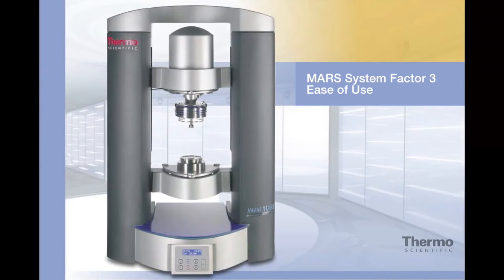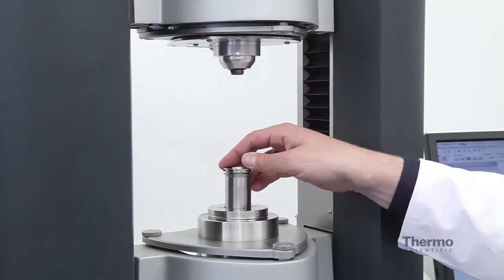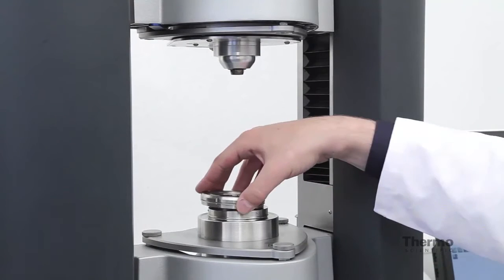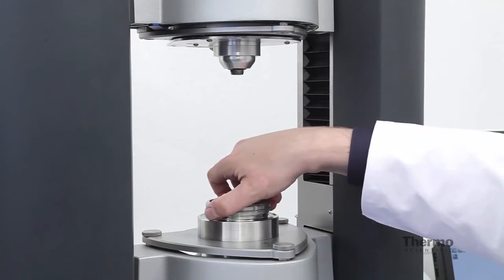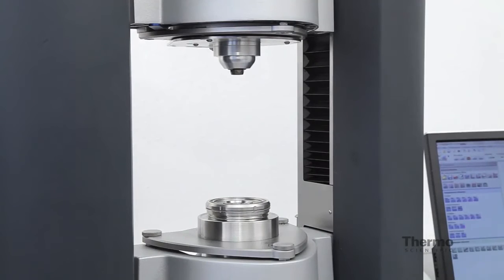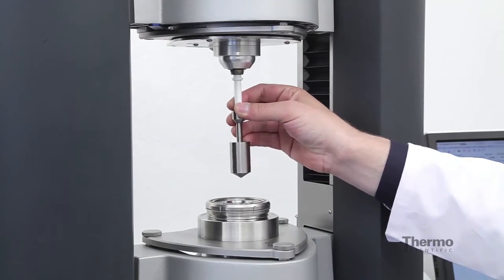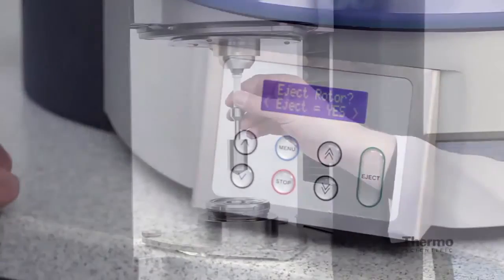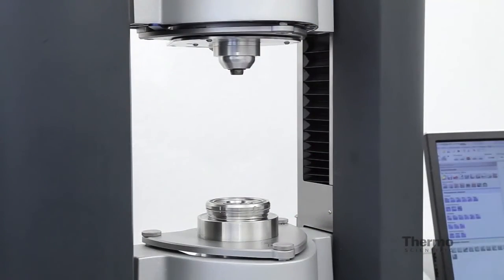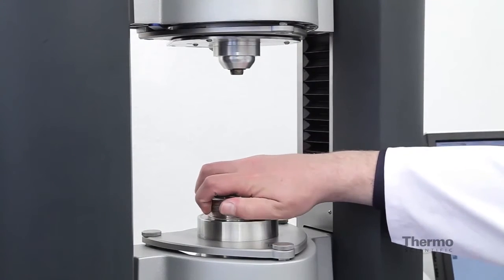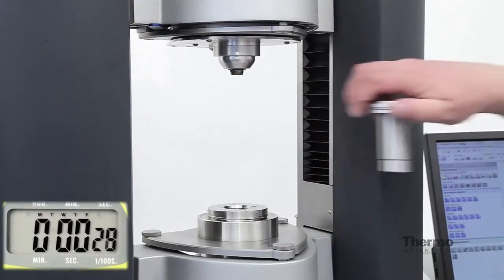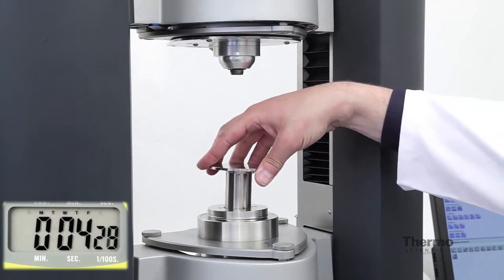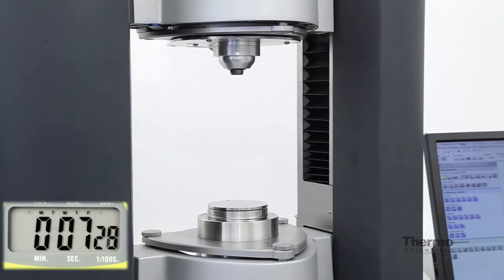Ease of use. Of course some of the well-known ease of use features from our previous MARS systems have been implemented into the new MARS. Like for instance, no matter if you want to work with Peltier temperature controlled cylinder geometries, the design for optimized temperature calibration or if you want to work with standard Peltier plate geometries, our measuring plate insert for the Peltier cylinder lets you do both within seconds of downtime.